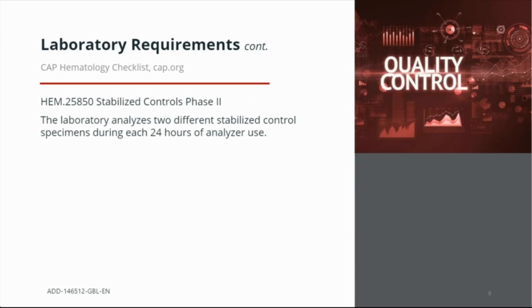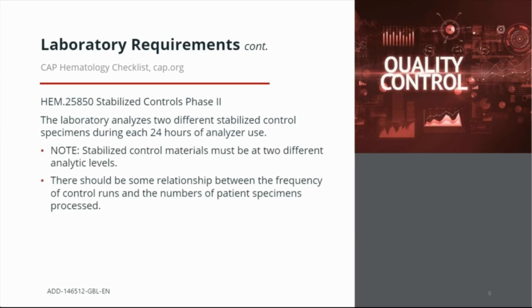Section HEM 25850 states the laboratory analyzes 2 different stabilized control specimens during each 24 hours of analyzer use, with the caveat that stabilized control materials must be used at 2 different analytical levels, and there should be some relationship between the frequency of control runs and the number of patient specimens that we process. So best practices, if we're only following the minimum, is preferably a normal and a high.